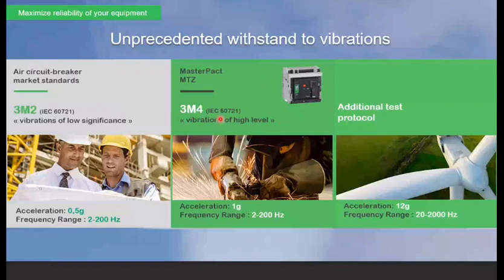Then coming to vibration, because of vibration you can see there is fretting corrosion, and because of fretting corrosion there is nuisance tripping. So in MTZ we have removed the direct male female mating contacts, and we have established plug type, ribbon type contacts with gold and nickel plated male female terminations. Because of this you will not get nuisance tripping in your installation if you have an MTZ installed. In those kinds of fretting corrosive atmospheres, you can go with the MTZ and it will ensure you will not get any nuisance tripping in the installations.